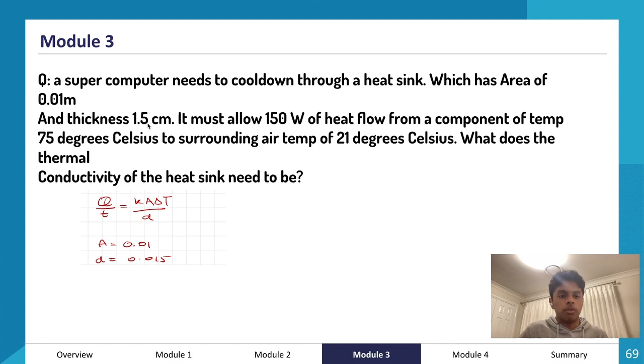So we have our equation, Q over T is equal to K A delta T over D. We have A is equal to 0.01 meters, thickness D equals 0.015 meters, which is 1.5 centimeters. We have the change in temperature to be 75 minus 21, so 75 is the temperature of the component and 21 degrees is the surrounding air temperature. So our delta T, change in temperature, is 54. And our Q over T, which is the joules over time, or change in energy, is equal to 150 watts. So we have all our data. What do we need? We're looking for the thermal conductivity constant of the heatsink, which is K.